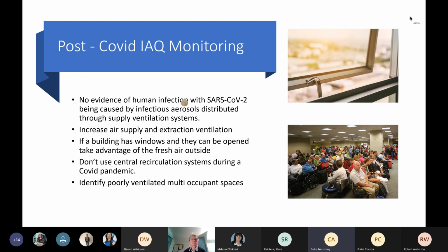Large spaces such as classrooms are well ventilated, but they can easily become overcrowded. Small rooms occupied by a couple of people show the highest probability of infection, even if they're ventilated. You may have internal rooms that don't have any ventilation other than the ventilation systems located in the outside corridors, maybe. I think ventilation to these spaces needs to be investigated and addressed in the current climate for the best future practice. The general recommendation is to stay away from crowded and poorly ventilated spaces. In buildings without mechanical ventilation systems, it's recommended to actively use openable windows.